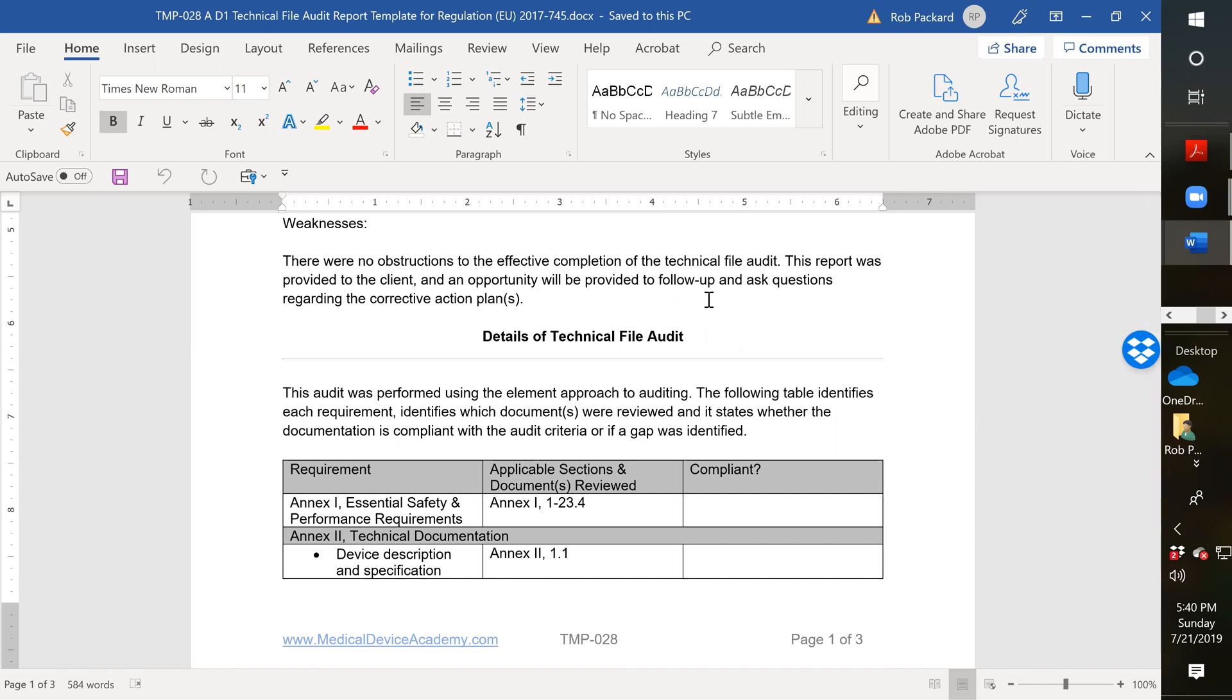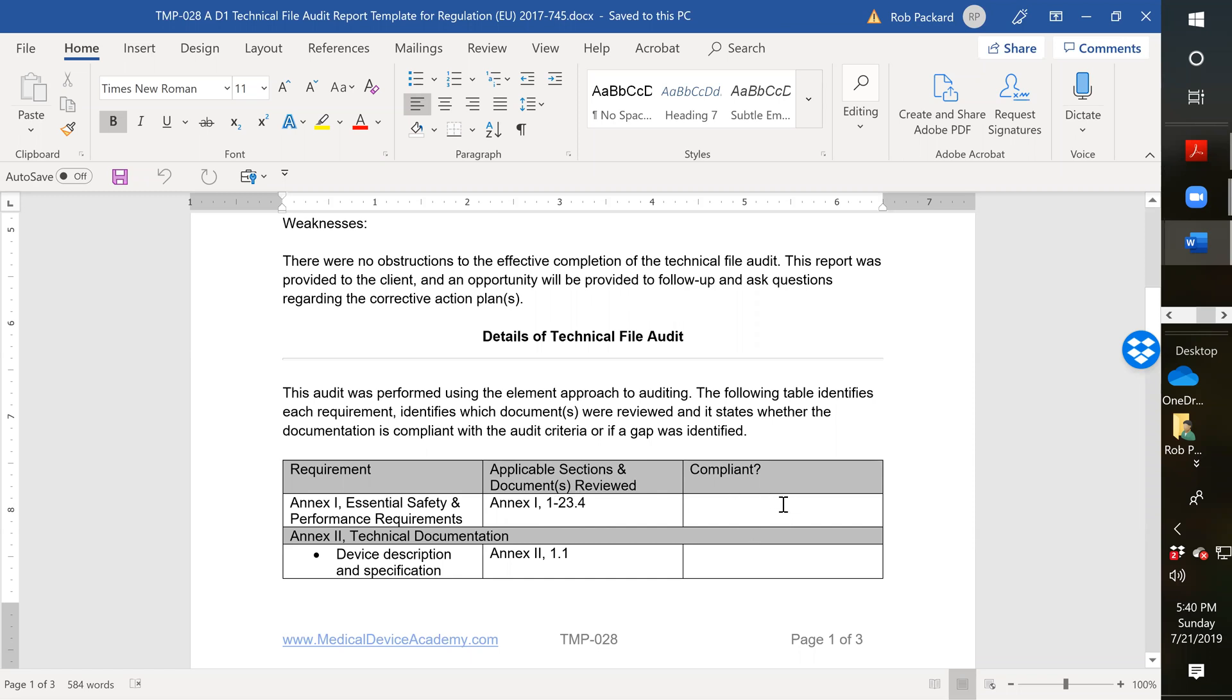But in this particular case where you're looking for technical file compliance, I think using a checklist approach or the element approach is a much better approach to making sure you have compliance of the technical file. So the first thing we start out with is Annex 1, the essential safety and performance requirements. This would be sections one through 23.4. I just have a box here that says compliant.